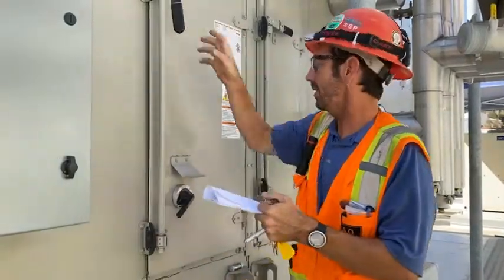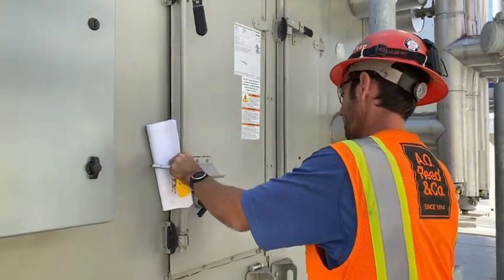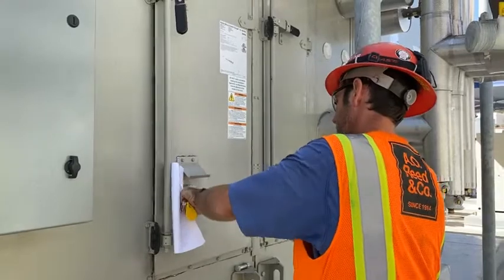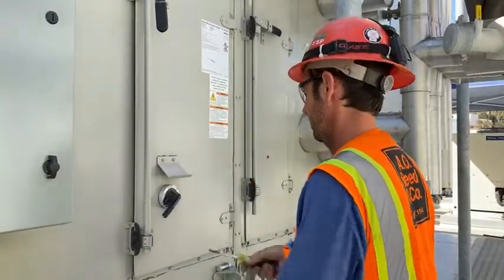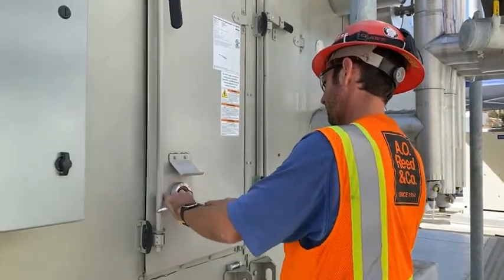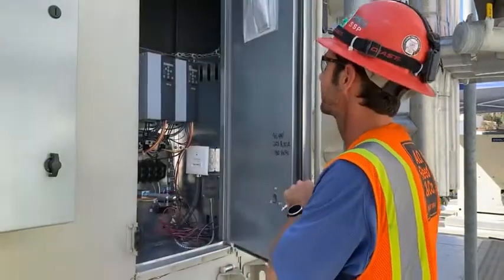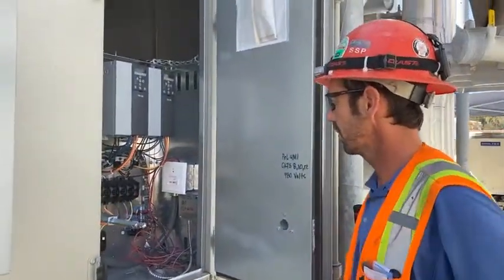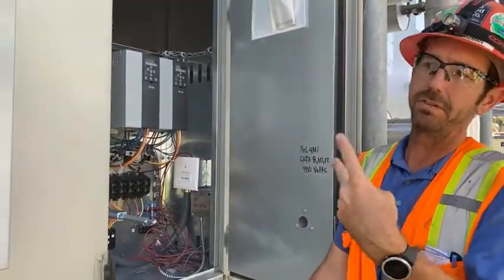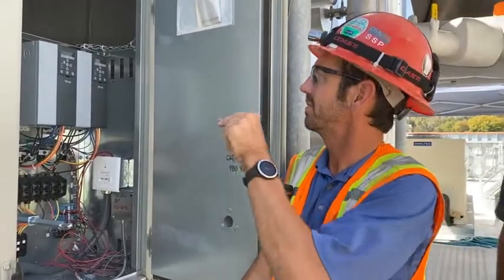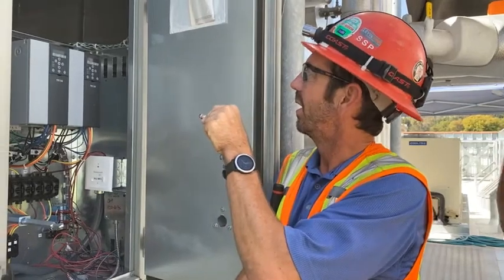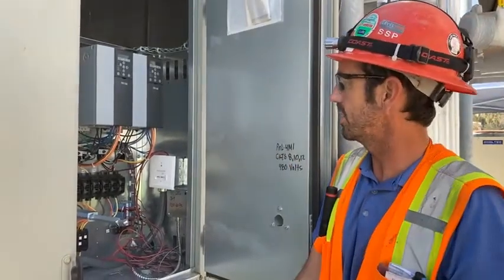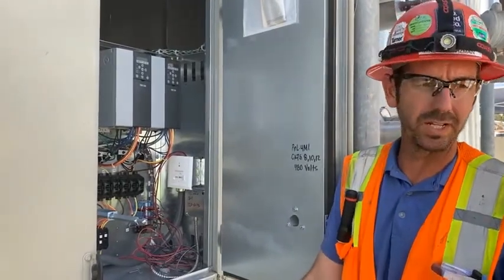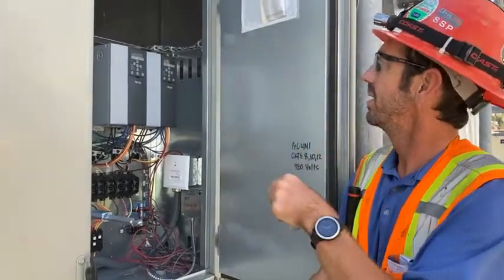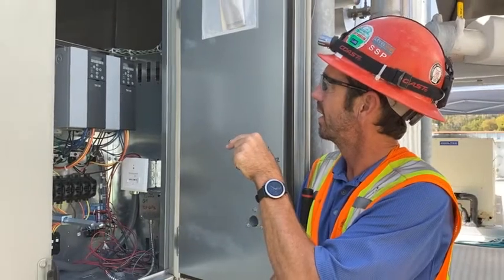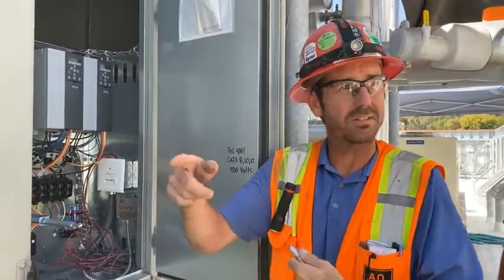Then we'll go into the controller, the electrical compartment. So like I mentioned before, we do have 2 fans. This is a double fan wall air handling unit. So we have 2 VFDs. VFD 1, VFD 2. We are in auto, which is good. So for some reason, the controls is not running this unit right now. Like I mentioned before in training, they're still finalizing the integration into this building. Okay, so we do want to leave them in auto mode right here. But they could also not be running because of that high pressure switch. I checked, the switch wasn't tripped.